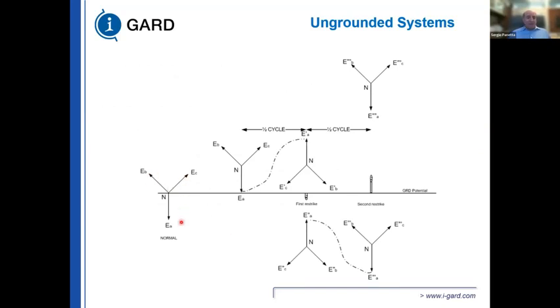So you can see that if you have a 3-phase system, when you have an intermittent arcing fault on an ungrounded system, on the first occurrence of a ground fault, let's say it's on A phase, A and ground are at the same potential. 1/2 cycle later, because there's no grounding system, all you're doing is charging the capacitance of the system. 1/2 cycle later, you're at 2 per unit on A phase with respect to ground. On the ungrounded system, you don't have a dead short to ground, but you have a deterioration of the insulation, so it sparks over. And when it sparks over, that gap created by the weakness in the insulation, now you're down to 2 per unit. And now 1/2 cycle later, you're at 3 per unit. And this keeps going on until your whole system collapses.